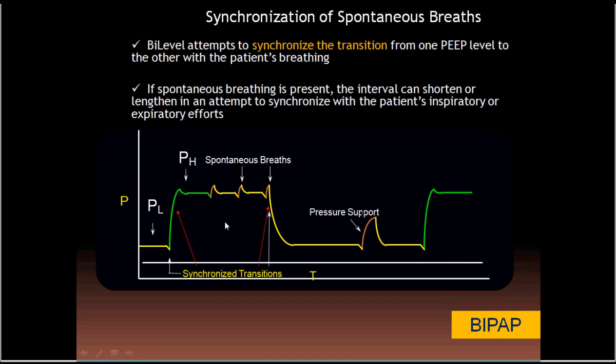Another important point: if the patient is apneic or paralyzed, you set a rate and the cycling will be started not by triggering but by time. If you set the high CPAP duration and a frequency of 15, this will cycle 15 times per minute. The difference between the low and high CPAP is responsible for delivering the tidal volume. If the patient starts to breathe spontaneously, he can take breaths at either the high or low level and will be assisted accordingly.